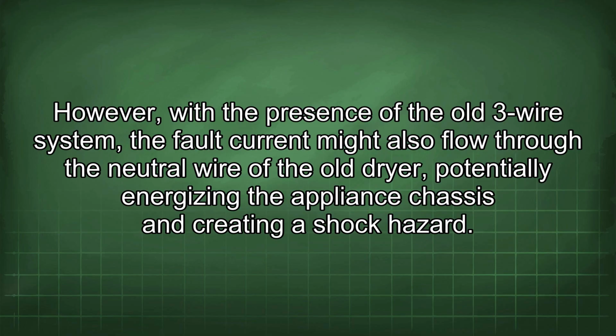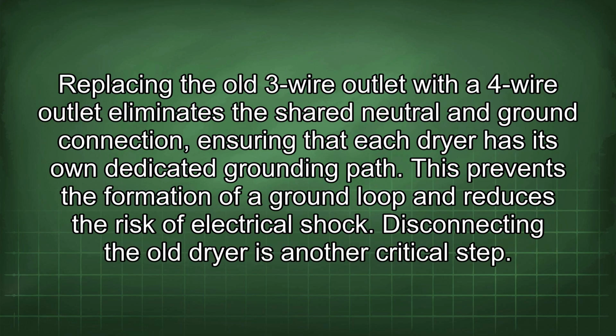However, with the presence of the old 3-wire system, the fault current might also flow through the neutral wire of the old dryer, potentially energizing the appliance chassis and creating a shock hazard. Replacing the old 3-wire outlet with a 4-wire outlet eliminates the shared neutral and ground connection, ensuring that each dryer has its own dedicated grounding path. This prevents the formation of a ground loop and reduces the risk of electrical shock.